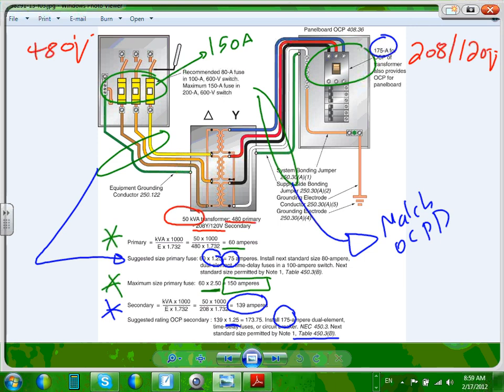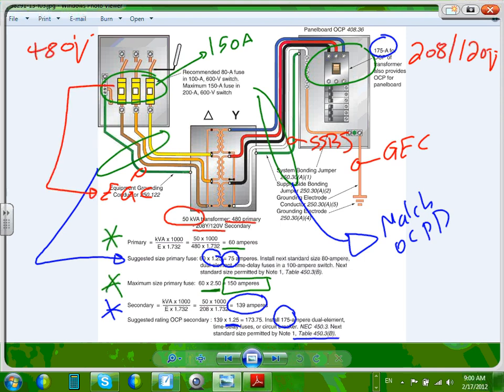Questions? Again, we will be doing calculation in commercial a lot. I want to bring to your attention a few things. Number one is this one, grounding electrode conductor, right at the service, separately derived system. Number two is supply side bonding jumper, this guy. And number three is equipment grounding conductor. Can you guys see these, the grounding stuff? Everybody knows how to size the equipment grounding conductor. How do we size the equipment grounding conductor? Based on the overcurrent protection device ahead of it. So the overcurrent protection device is 150 right here. I can size the equipment grounding conductor.